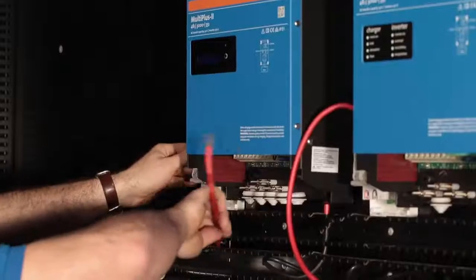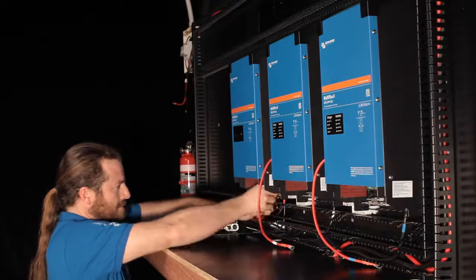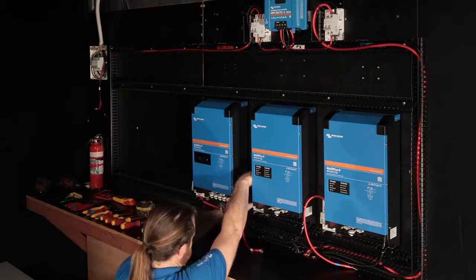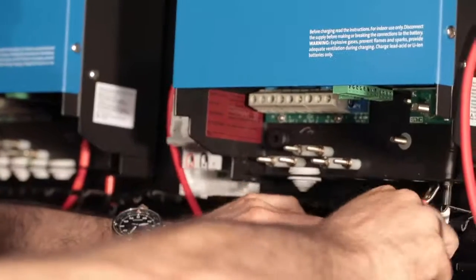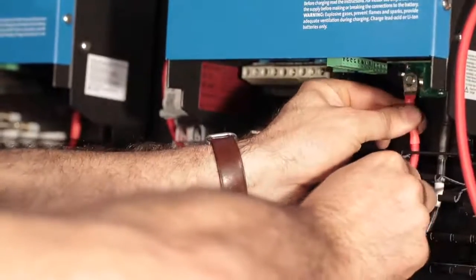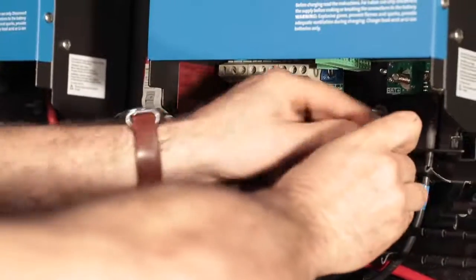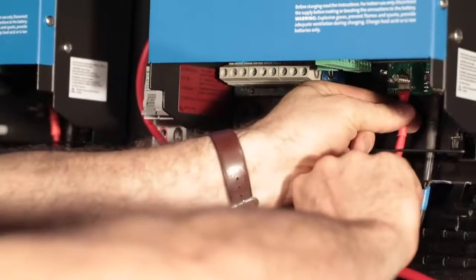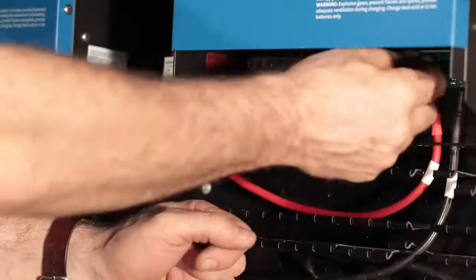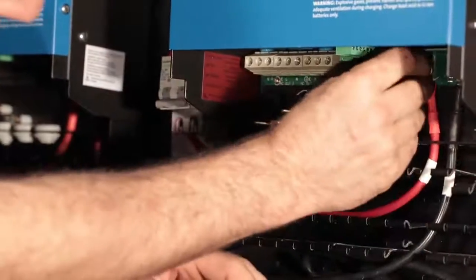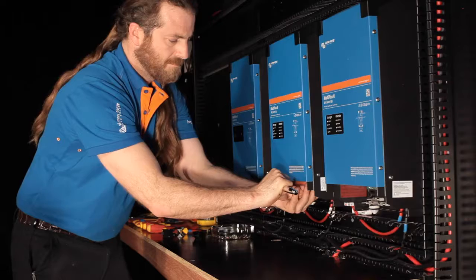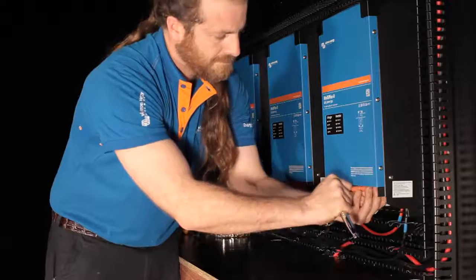It's important when you're inserting cables to make sure there's no stray copper wires that might cause a short circuit. Insert the cables through the glands in the bottom of the Multiplus 2s, making for a neat installation. It's also important to make these connections before you connect any battery or power. Connect the cables in the same way you connect the negatives, with the flat washer, then the spring washer, then the nut. And double check the cables for firmness and good connection.